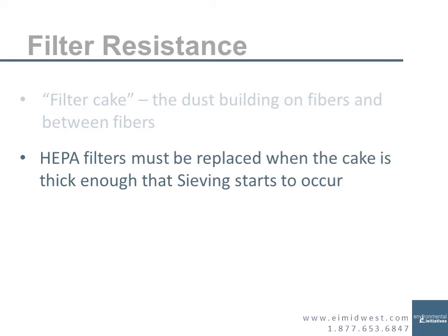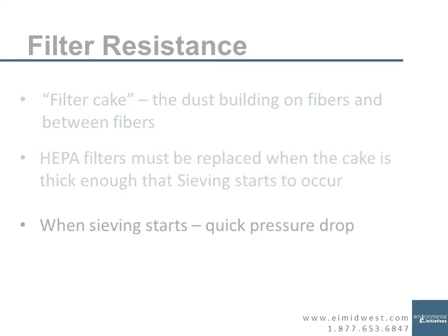Right? At that point, we need to remove the filter. And of course, the reason why many HEPA equipment has a pressure gauge is that if your pressure gauge all of a sudden spikes, you know the HEPA filter or the pre-filter has to be replaced because boom, it's so full, pressure is now incredibly high on one side versus the other side.